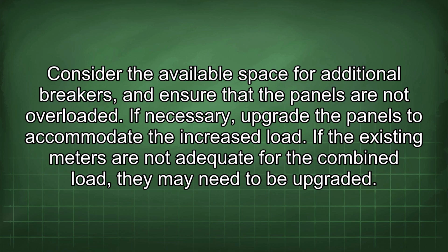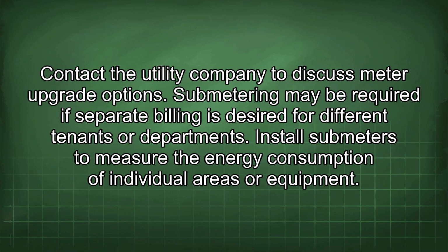If the existing meters are not adequate for the combined load, they may need to be upgraded. Contact the utility company to discuss meter upgrade options. Submetering may be required if separate billing is desired for different tenants or departments. Install submeters to measure the energy consumption of individual areas or equipment.